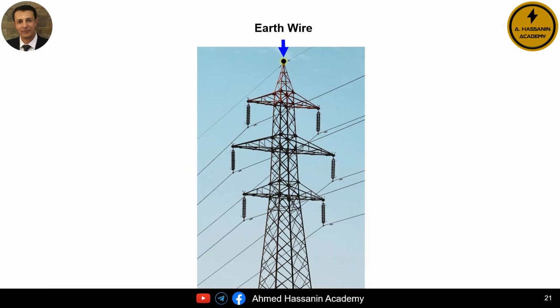To better understand the concept of the protection angle or protection zone, and the reason for having either one earth wire or two earth wires on some overhead transmission lines, let us consider, for example, a transmission tower for a certain electric voltage. In the image before us, there is one earth wire located at the highest point of the tower and extending along the length of the overhead transmission line.